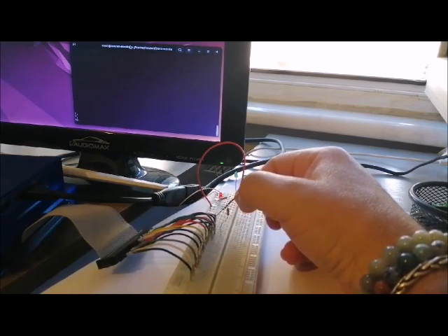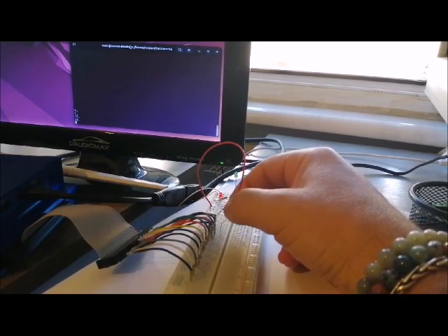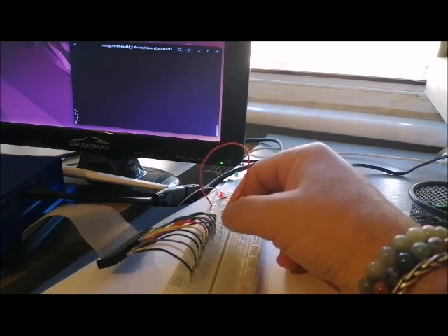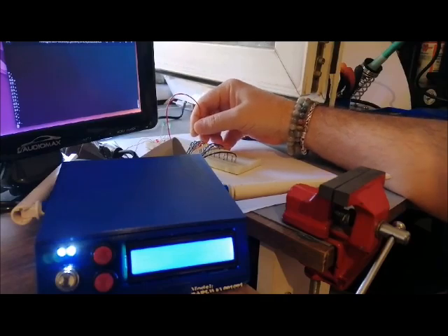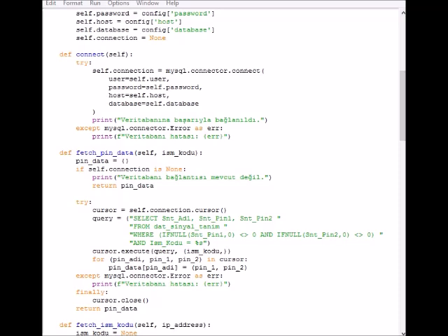For example, if there is a definition that pins 7 to 12 and pins 9 to 12 should short circuit, the system will automatically detect, according to Kirchhoff's law, that pins 7 and 9 must also short circuit. It will also check whether the personnel is authorized to perform this test, among many other controls.